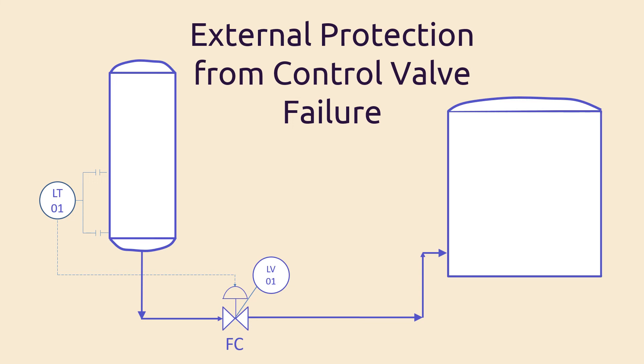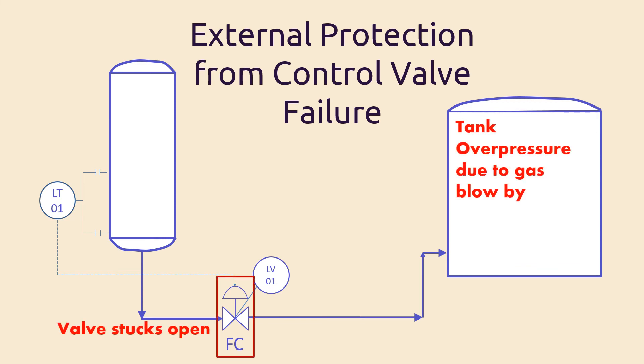So what if the valve mechanically stuck in the open position? This would mean that the vessel will be emptied from the liquid. After emptying the vessel, the gas in the vessel starts flowing to the tank. This means that the pressure starts to rise, which shall cause over-pressure in the tank. This can cause the welding between the tank shell and roof to fail, which shall lead to gas exposure to the atmosphere — a safety and environmental disaster. This is called the gas blow-by case.